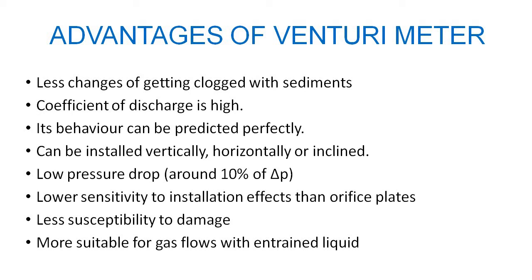We are dropping the pressure for measuring the flow, but we are not dropping the pressure up to, we can say, 10 percentage. Lower sensitivity to the installation effect than the orifice plate. Less susceptible to damage. More suitable for gas flow with entrained liquids.